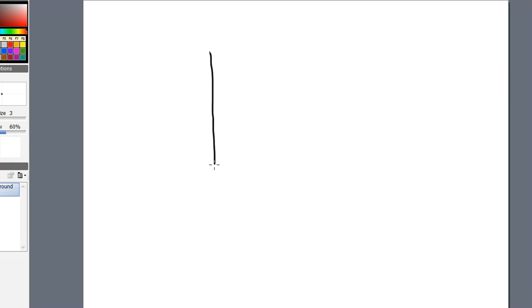So when this system makes a calibration curve, it's going to say, oh, okay, I've got a pH of 4, I've got a pH of 7, and I've got a pH of 10. And what I'm going to see is a straight line that gets plotted onto a graph. So this straight line needs to be a straight line. And if I only pick 2 buffers out of the system, any 2 points make a straight line. So yeah, 2-point calibrations are better than 1-point. But 2 points are still not ideal because any 2 points make a straight line.